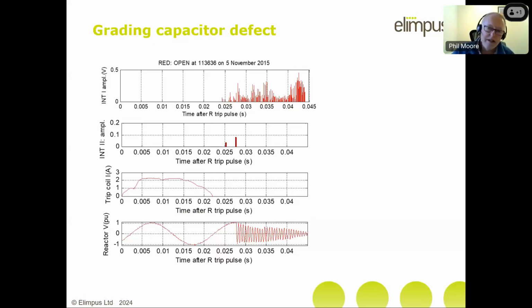Here's the result. This is almost 10 years ago, November 2015, back before we had quite the equipment that I'm using today. But anyway, we were able to measure the trip coil, so you can see the trip command occurred at 0 there. Again, we had this idea of using E-field sensors, which gives us the point at which the current interrupts, going from the 50 Hertz to the transient there. So this is the terminal voltage of the reactor.